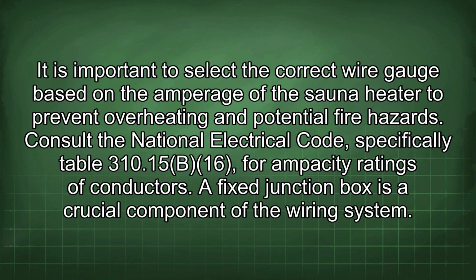It is important to select the correct wire gauge based on the amperage of the sauna heater to prevent overheating and potential fire hazards. Consult the National Electrical Code, specifically Table 310.15(B)(16), for ampacity ratings of conductors.